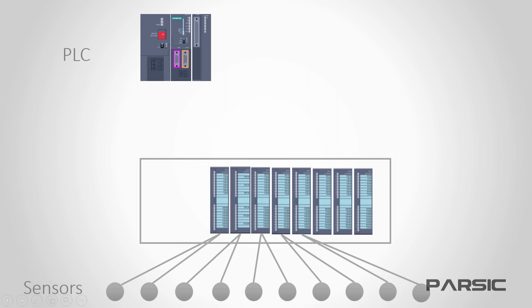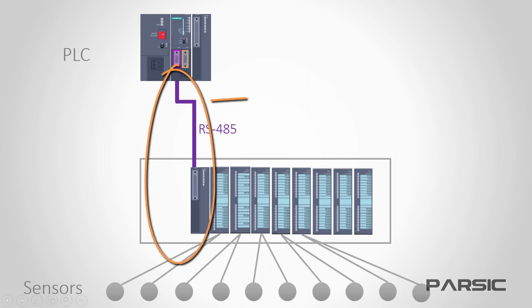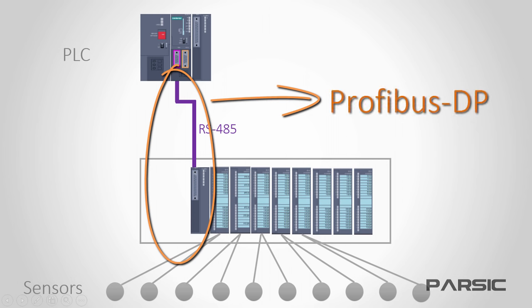Now, to enable data transfer between the PLC in the control room and the I.O. modules in the new enclosure, we're going to install an I.M. or interface module here. Then we can use Profibus DP and an RS-485 cable to transfer all data.